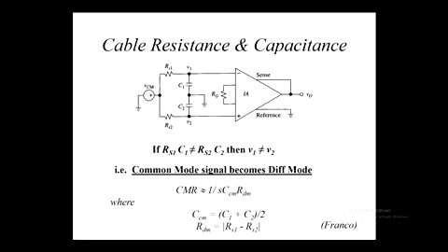They might age, resistance increase. So I don't know whether it's apparent, but for any common mode signal, if it's being applied equally to both electrodes, and maybe the electrodes have aged a bit and become more resistive, or they've broken off.